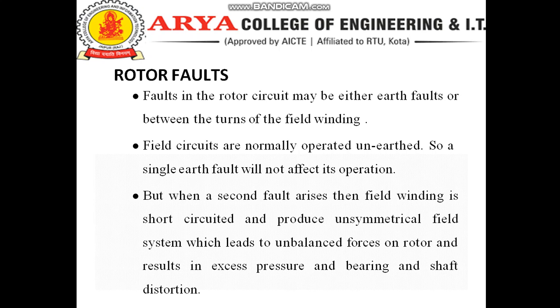Now we discuss the rotor faults. The faults in the rotor circuit may be either earth faults or faults between the turns of the field winding. Field circuits are normally operated unearthed, so a single earth fault will not affect its operation. But when a second fault arises, the field winding is short-circuited and produces an unsymmetrical field system, which leads to unbalanced forces on the rotor and results in excess pressure and bearing and shaft distortion.